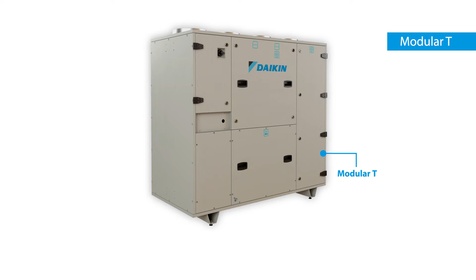The next product I'd like to speak about today is the Modular T. It's another solution for decentralized ventilation with a counterflow plate exchanger, but this time with a vertical layout. It's again a standardized, made-to-stock solution, just like the Modular L, and it comes in 5 sizes, all with right and left handing. Thanks to its reduced width and low footprint, it's the ideal solution for new and existing buildings. Airflow range goes from 150 up to 4,100 cubic meters per hour, with the highest filtration grade again being ePM1 80%.